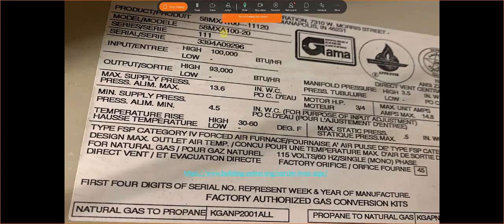But this 100 right here, this is going to tell you what size BTU the system is, okay? So I know that this is a 100,000 BTU system. If it was a 080, 80,000, or a 060, 60,000, and so forth. If I didn't have that information, I can look at the input here, and I would see it's a 100,000 BTU system.